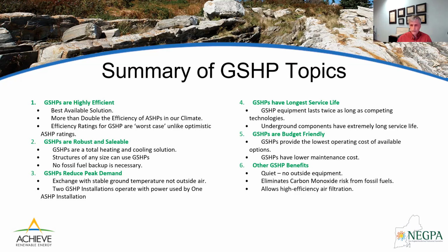Ground source heat pumps also have a very long service life, lasting about twice as long as competing technologies. And the main reason for that is that the equipment is all inside. There's no outside heat exchanger that's subject to the ravages of salts near the coast or other things that can corrode that external heat exchanger. The underground components have an extremely long life, typically estimated to exceed 100 years. So when ground source heat pump systems need to be updated, it's the indoor equipment that's updated. The underground heat exchanger would remain the same, unless the building were somehow substantially being increased in size.